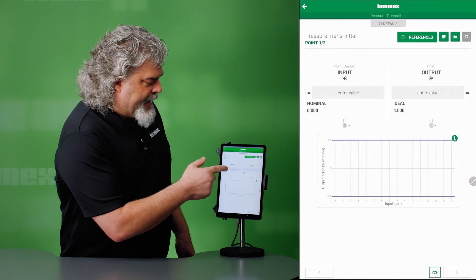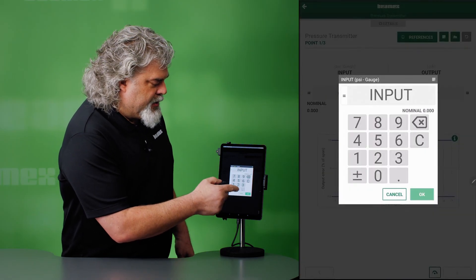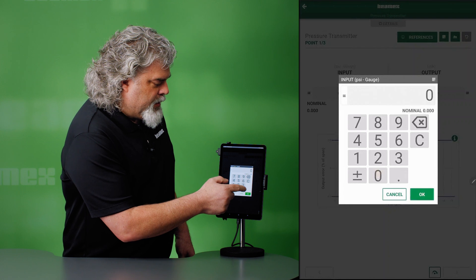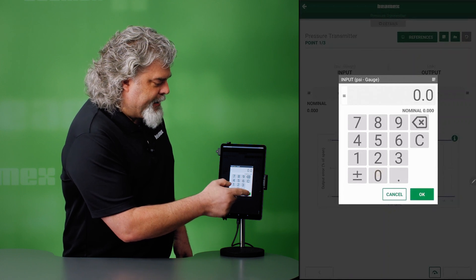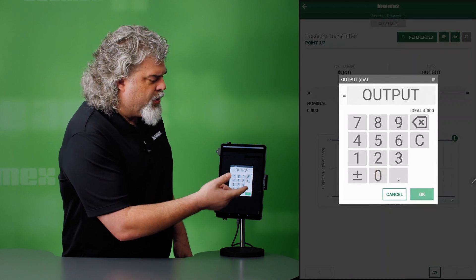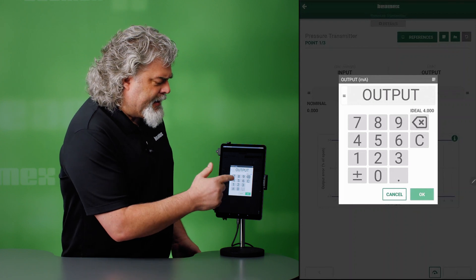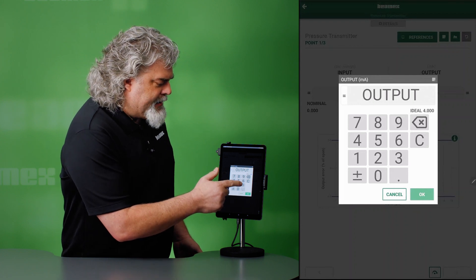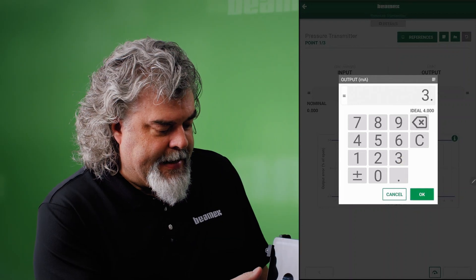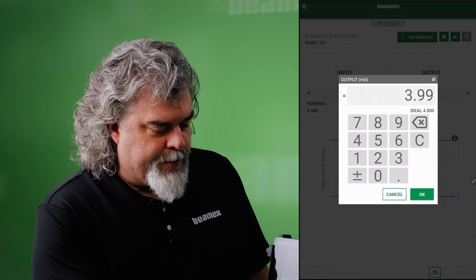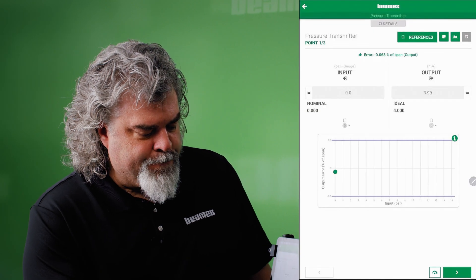Nominal value, we're starting off at zero. And say that my calibrator here, my reference is showing 4.00 milliamps is my expected output. And 3.99 is literally what I'm measuring here. So let me hit OK on that.